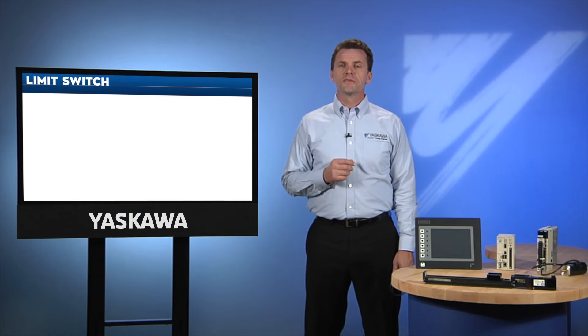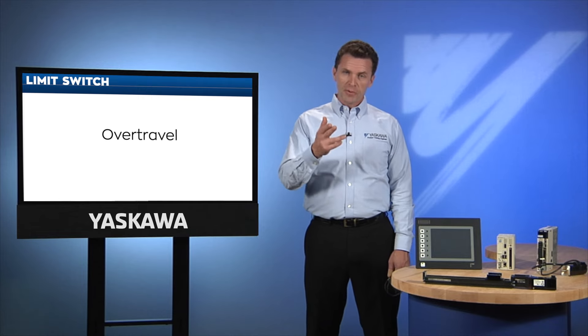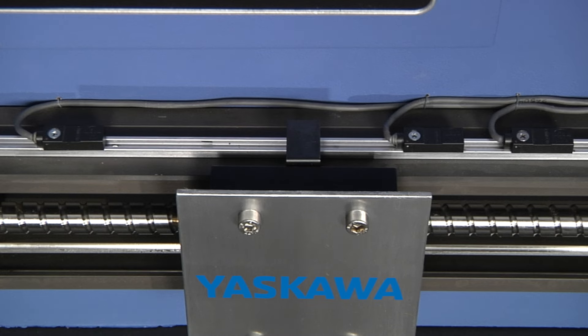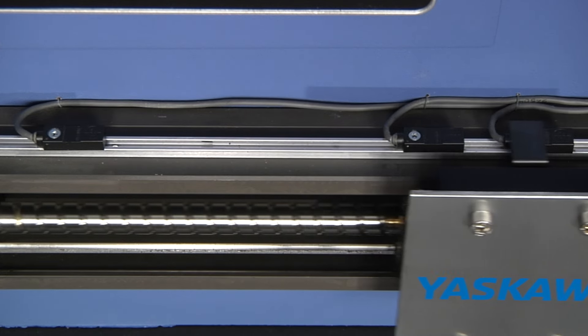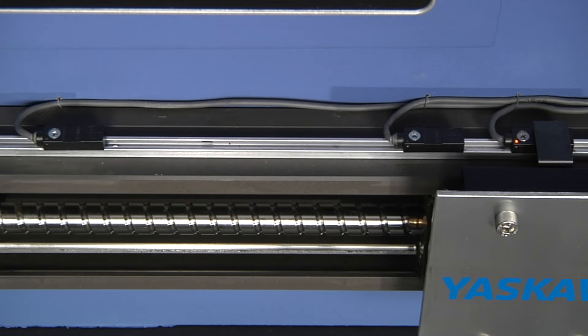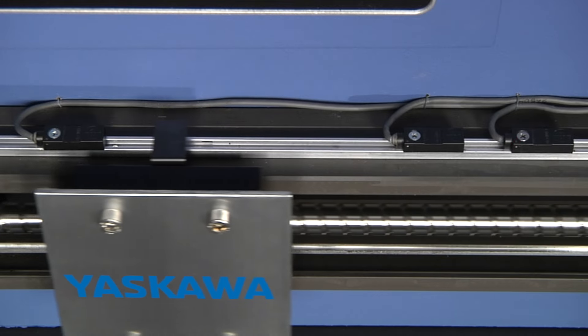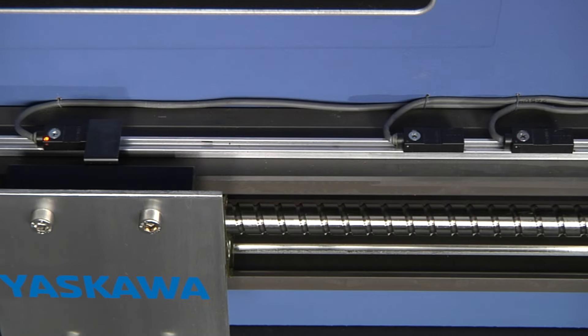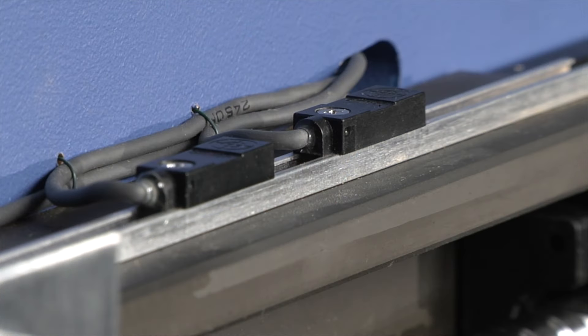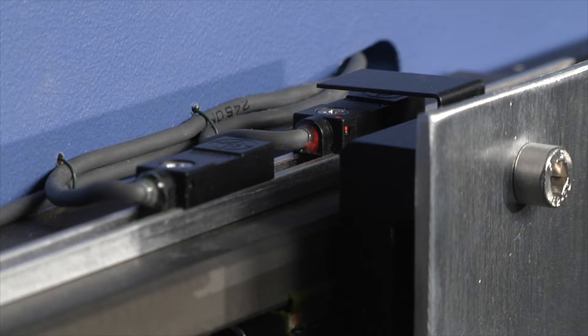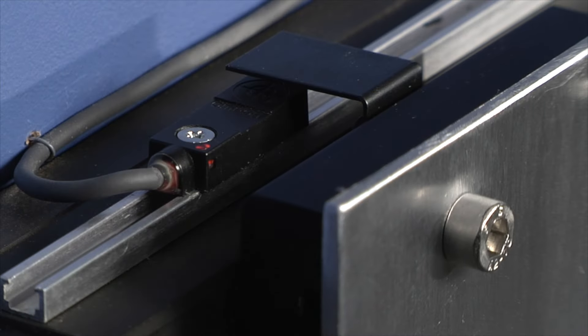Another direction-sensitive feature found in amplifiers is over-travel, which some people refer to as the limit switch function. Over-travel is an amplifier input that stops the motor from moving in one direction — one input for forward and another input for reverse. We establish the boundaries of over-travel by placing a sensor at each end of the machine's range of motion. A properly programmed controller should prevent the machine from ever getting close enough to reach these sensors, but experience dictates the wisdom of planning for the unexpected. Over-travel inputs can prevent costly damage; without it, moving parts of the machine could be allowed to crash into one another.